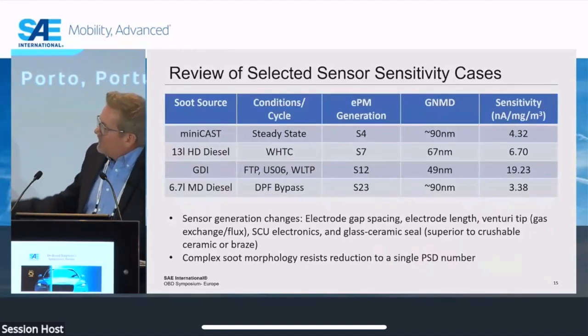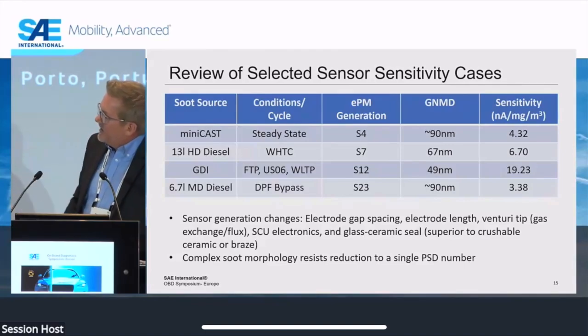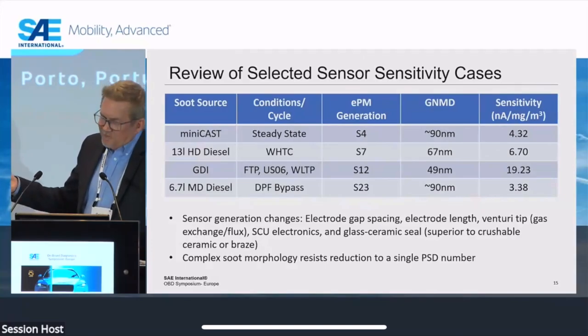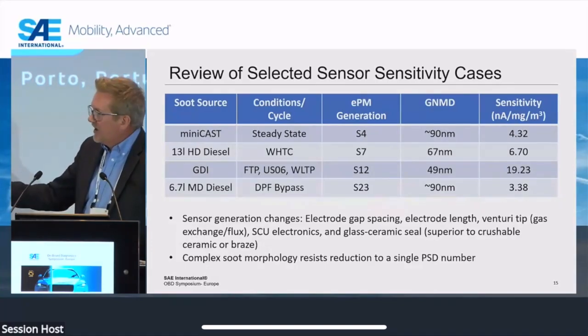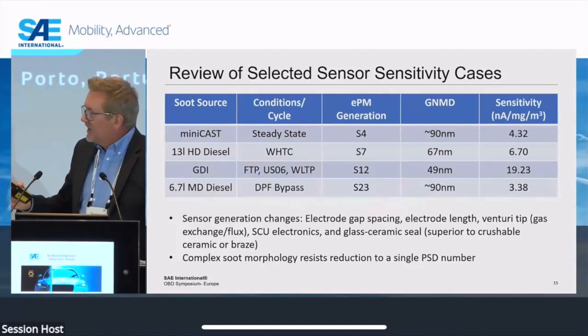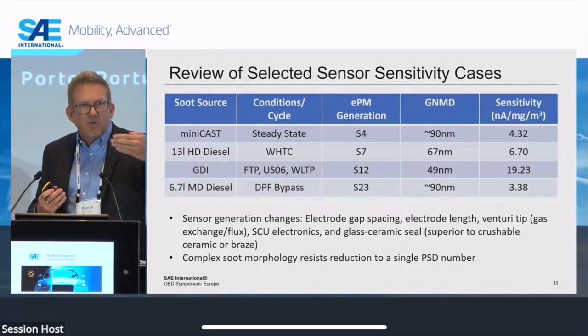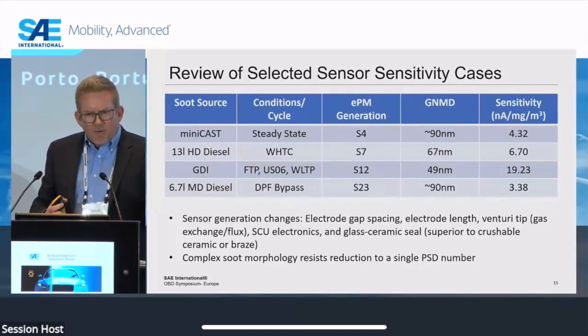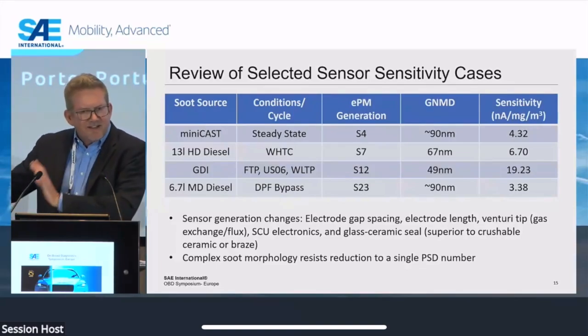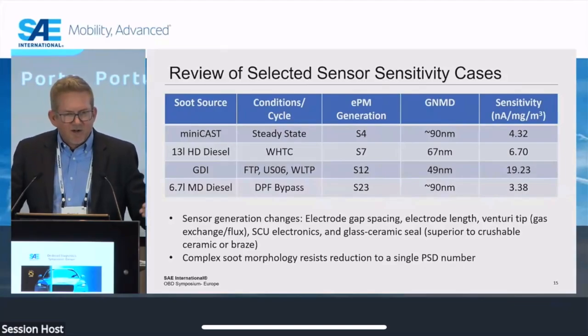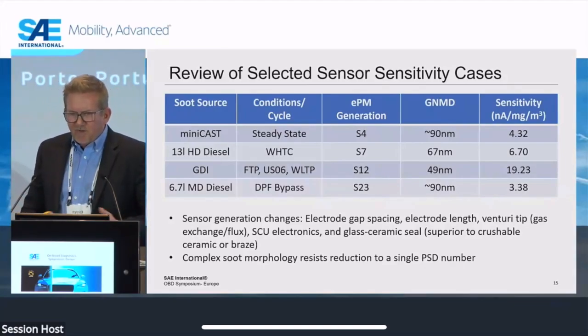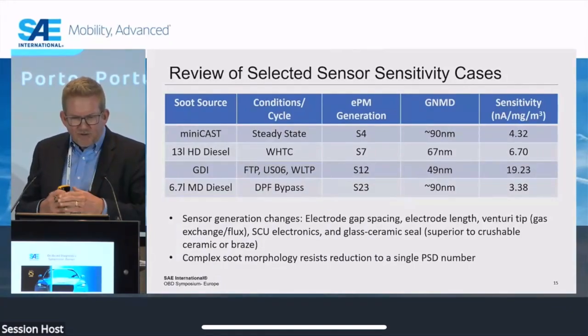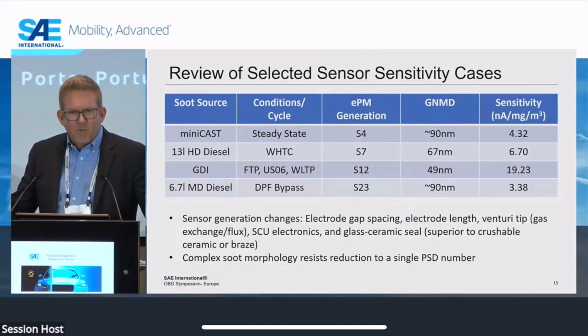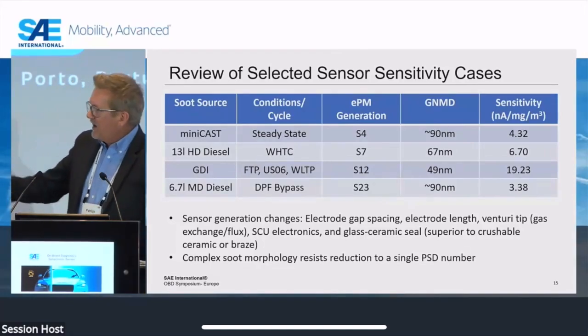So, summarizing those 4 examples: different soot sources, of course, different engines, in one case not even an engine, but just a generator, different conditions, steady states, various drive cycles, the bypass. Unfortunately, the reality is different generations of our sensors, which can change electrode gap spacing, electrode length, the Venturi tip itself, how much gas exchange we want to pull through the sensor. For example, are we really interested in idle and low load conditions, or in wide open throttle conditions, and where do we shift that around? The Venturi tip, and Continental did a lot of this work, is actually pretty linear over a relatively wide range of exhaust gas velocities, but that has been a variable as we moved along.